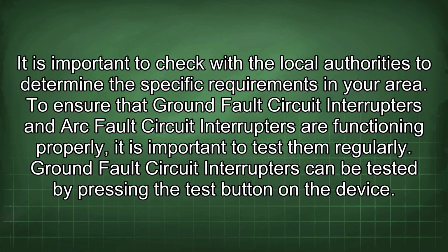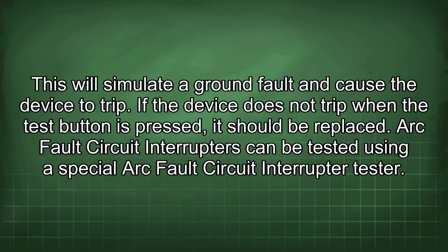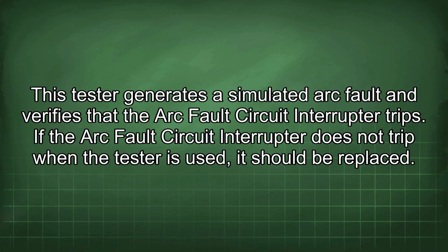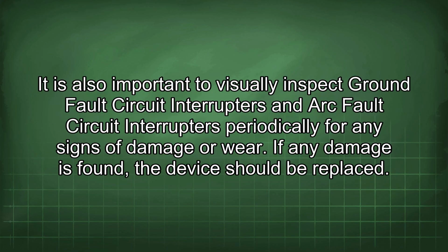To ensure that ground fault circuit interrupters and arc fault circuit interrupters are functioning properly, it is important to test them regularly. Ground fault circuit interrupters can be tested by pressing the test button on the device. This will simulate a ground fault and cause the device to trip. If the device does not trip when the test button is pressed, it should be replaced. Arc fault circuit interrupters can be tested using a special arc fault circuit interrupter tester. This tester generates a simulated arc fault and verifies that the arc fault circuit interrupter trips. If the arc fault circuit interrupter does not trip when the tester is used, it should be replaced. It is also important to visually inspect ground fault circuit interrupters and arc fault circuit interrupters periodically for any signs of damage or wear. If any damage is found, the device should be replaced.